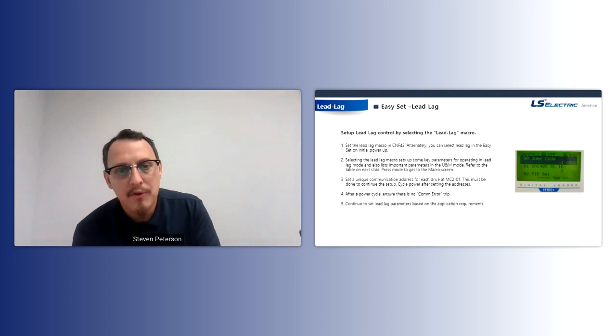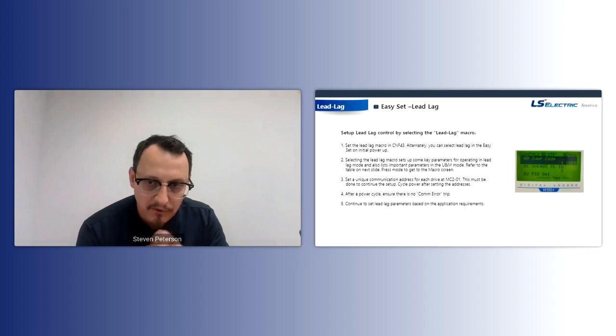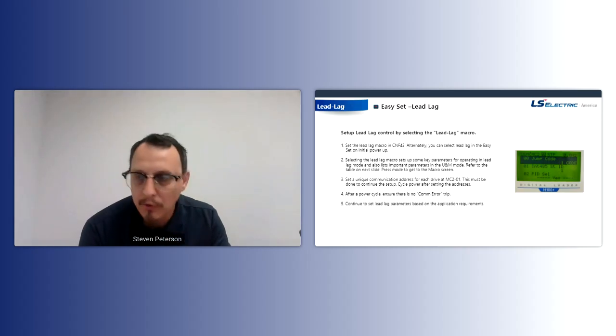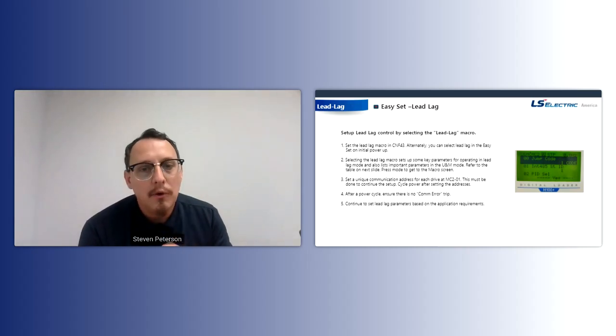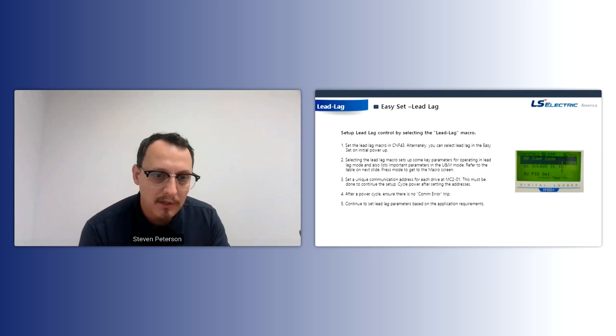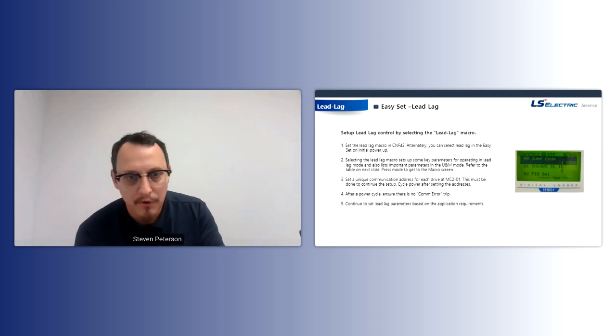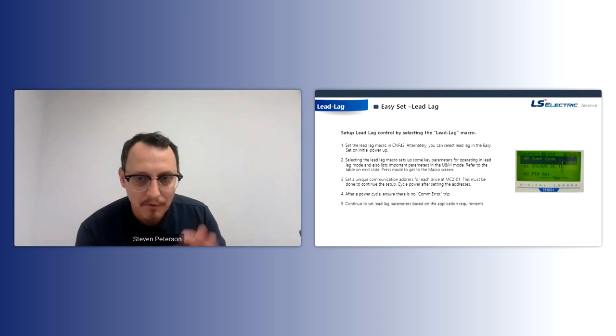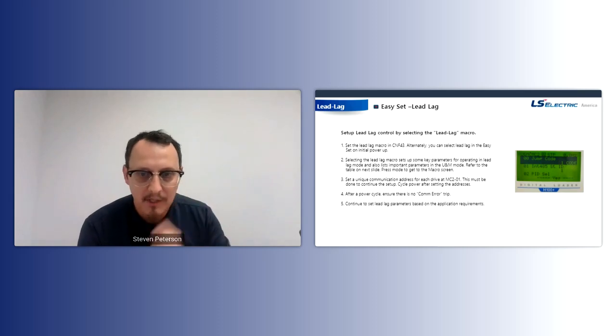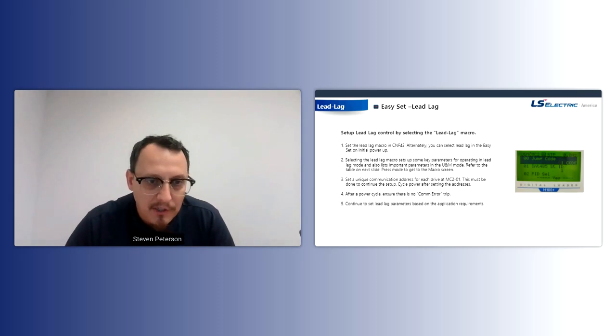Drive 2 is going to be address 2. We default to 0, so it's a way of forcing you to put an address in there. With Modbus, everything needs to be unique. You need to uniquely say this is drive 1, this is drive 2. There can't be 2 drive 1s, there can't be 2 drive 2s. Okay, so that needs to be set up correctly. That's the first thing you do.